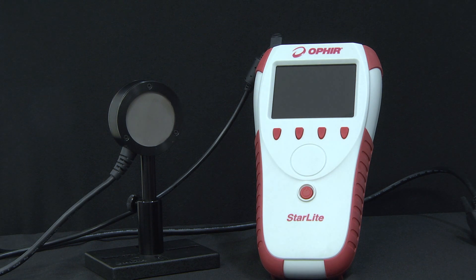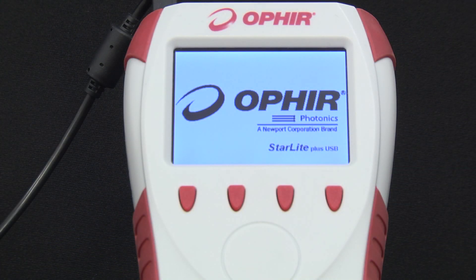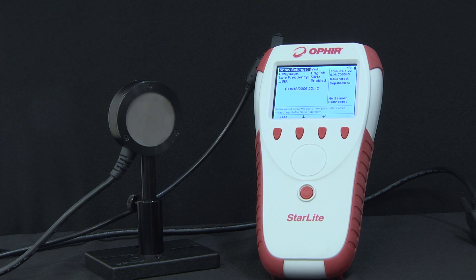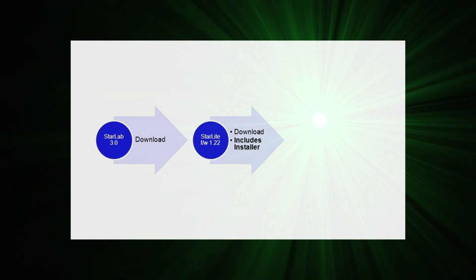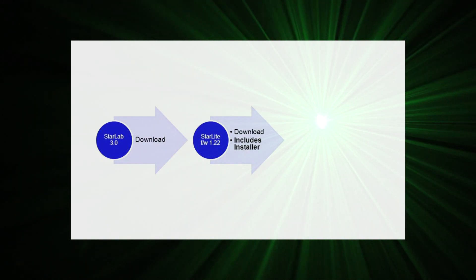USB connectivity to a PC is available for the StarLite as an add-on option. Enabling the USB connectivity makes it possible to connect the StarLite to a PC on which the StarLab software application is running. USB connectivity can either be ordered independently for a StarLite that you already have, or a new StarLite can be ordered with USB connectivity already enabled. There are three prerequisites: one, StarLab version 3.0 or later needs to be running on the PC — the latest StarLab application can be downloaded from the Ophir Photonics Group website. Two, the StarLite's internal ROM version must be at least 1.22 or later, which can also be downloaded from the Ophir Photonics Group website — the download includes an installer tool and instructions for performing the ROM version upgrade.